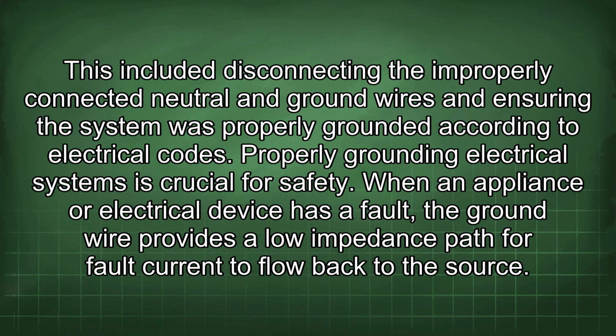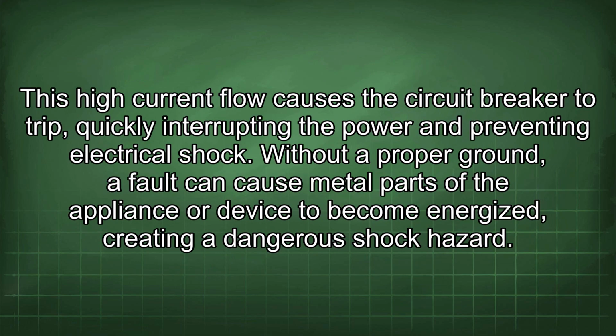This included disconnecting the improperly connected neutral and ground wires and ensuring the system was properly grounded according to electrical codes. Properly grounding electrical systems is crucial for safety. When an appliance or electrical device has a fault, the ground wire provides a low impedance path for fault current to flow back to the source. This high current flow causes the circuit breaker to trip, quickly interrupting the power and preventing electrical shock.